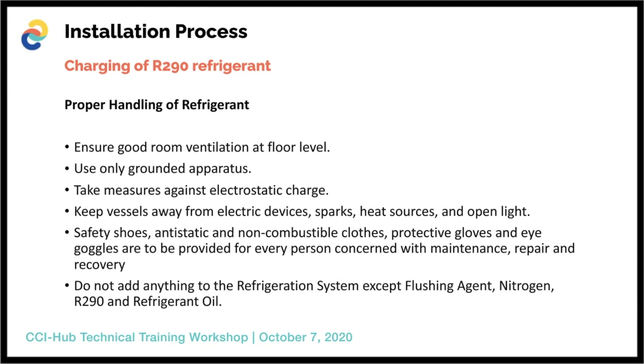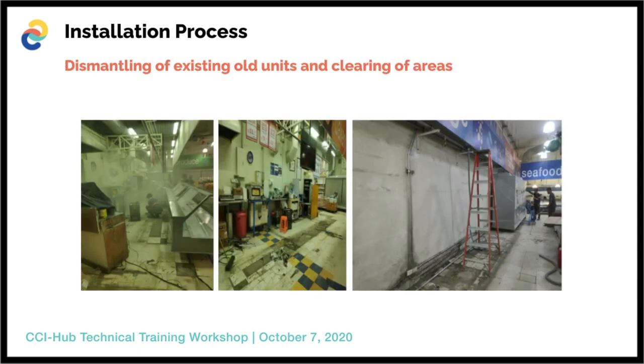So let me just add to that a little bit, just to give a little color to the challenges these guys had during this installation. One of the benefits, or the flexibility, of the R290 water loop system is being able to install it in existing stores. Though that is possible, it's by no means easy. As a matter of fact, it would probably be much easier for us to install a brand new store than an existing store, due to the limited hours that we're able to operate.